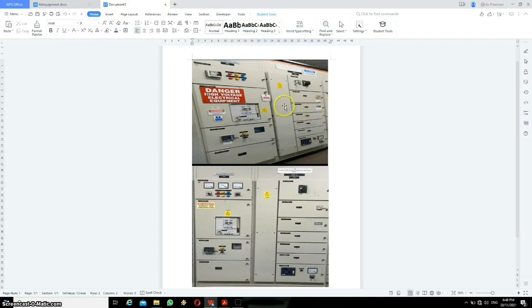For that, we need to ask permission from the consumer side to turn off the power supply to the load. As they give permission, then we need to turn off the overcurrent and earth fault relay as well. This is the overcurrent and earth fault relay, so we turn this off as well.